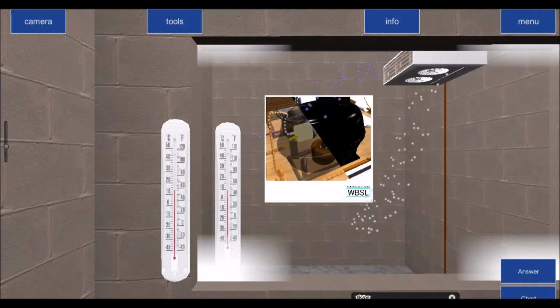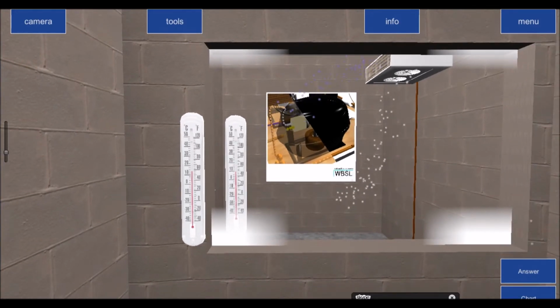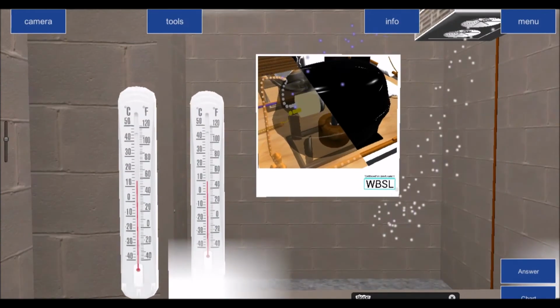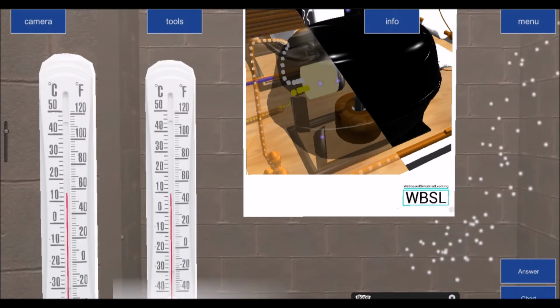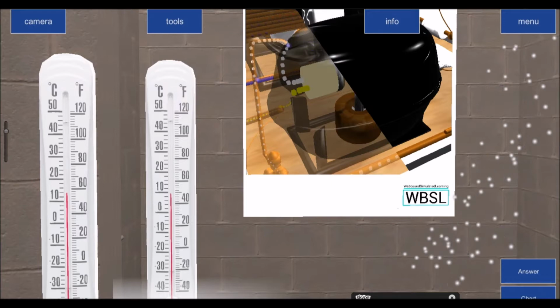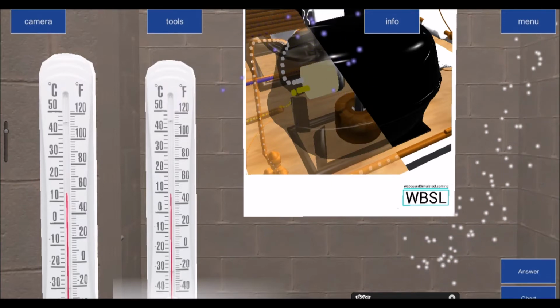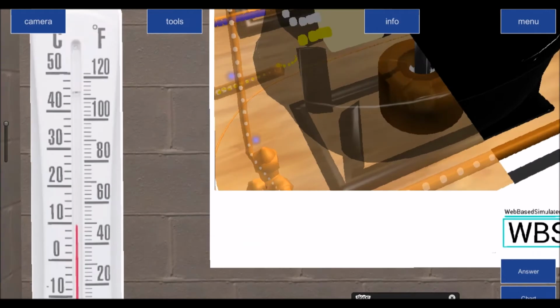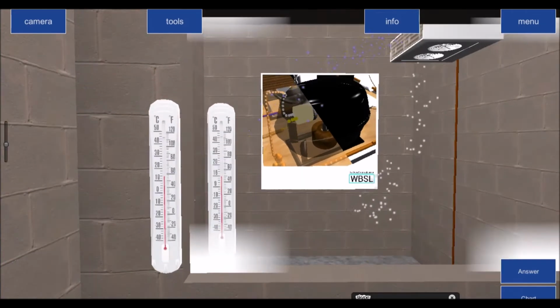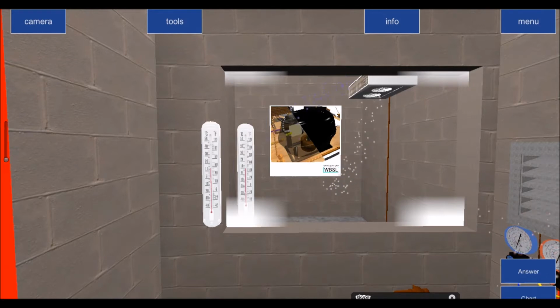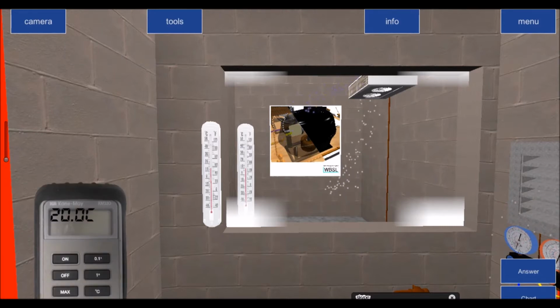Now again, we come across another system here, and we find that our system here is not working, and the reason why it's not working is because we can see that the room temperature here, just looking at the cold room thermometer, is at 10 degrees. So this should be down at 2 degrees. This chill room should be down at 2 degrees, but we see that it's at 10 degrees. So therefore, we need to find out, well, why can't we get this room down to 2 degrees? What is the problem with this room that it is not getting down to 2 degrees? And again, I'm going to use my thermometer. I'm not going to use my gauges. That's the last resort. I will only put my gauges on to determine what the problem is.